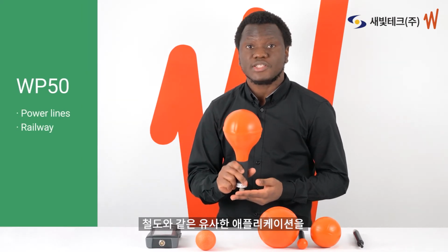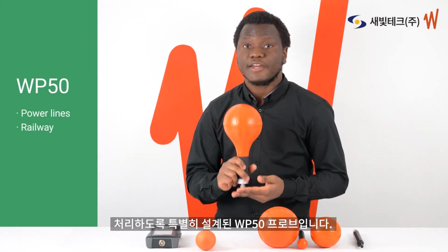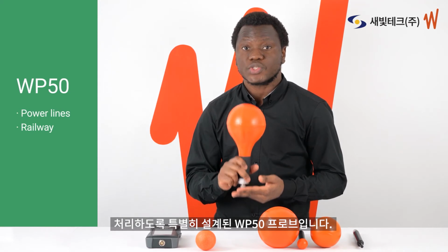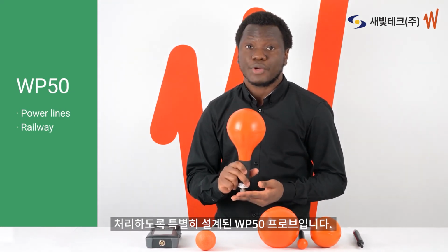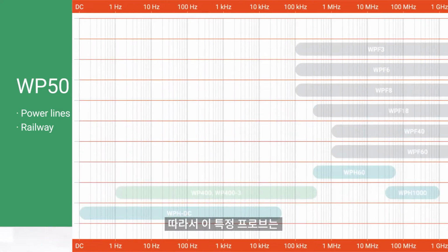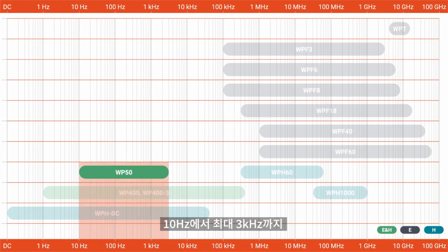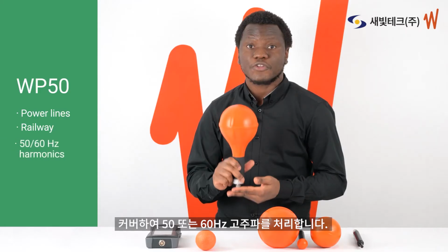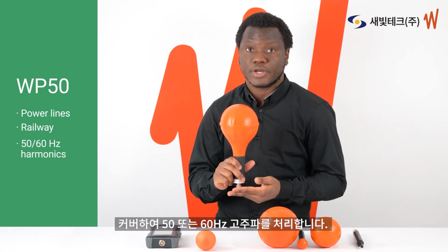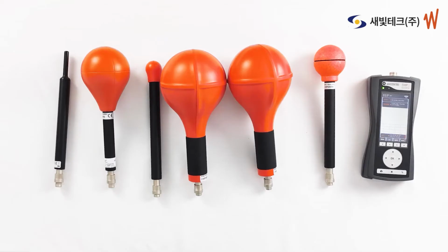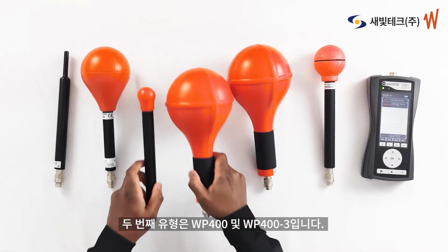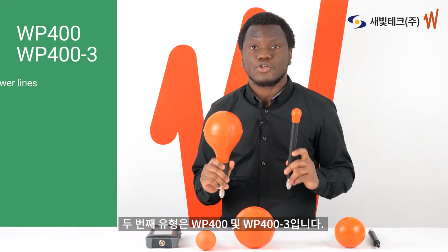The first is the WP50 probe, which is specially designed to cover power line frequencies measurements and also similar applications like railway. So this particular probe covers from 10 Hz up to 3 kHz to cover the 50 or 60 Hz harmonics. The second type is the WP400 and the WP400-3.